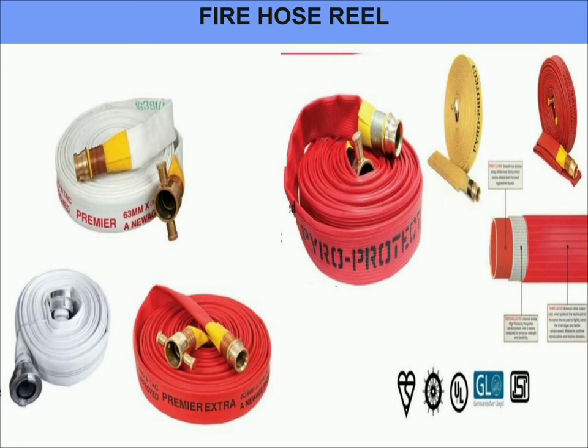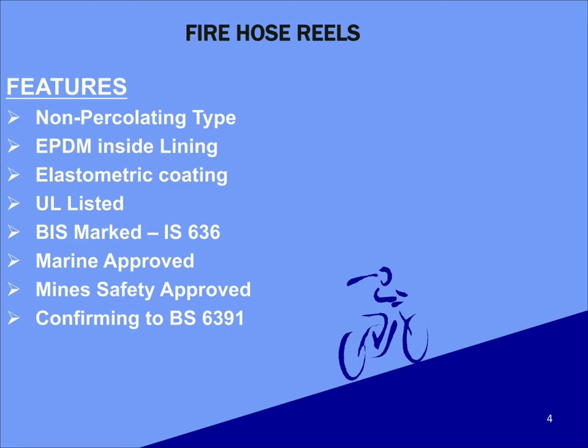Non-percolating hoses are generally used in fire services. Non-percolating hoses consist of a reinforced jacket made from polyester or nylon yarns. This type of hose has an inner lining of vulcanized rubber which is fixed to the jacket with adhesive. The use of non-percolating hoses is recommended in certain applications as frictional losses will be much less than that of percolating hoses. Coming to the other features of fire hose reels, they will have an EPDM inside lining — EPDM means Ethylene Propylene Diene Monomer Rubber — a class of rubber under ASTM standard D1418.